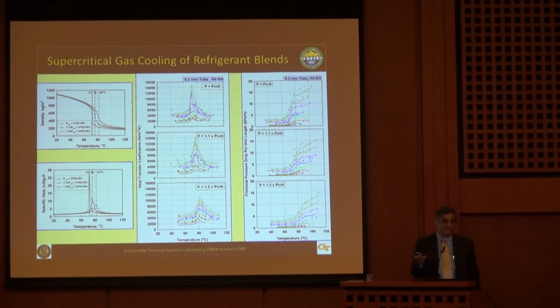Through very careful experiments we were able to track this peak in heat transfer coefficients, and also track this change in pressure drop. It behaves like a gas, and then suddenly, at the critical point, it changes to liquid-like behavior - for the same mass flux and same tube, the pressure drop suddenly changes by an order of magnitude. We were able to measure those and develop models for that, so now we can use these better fluids for vapor compression heat pumps and other systems.